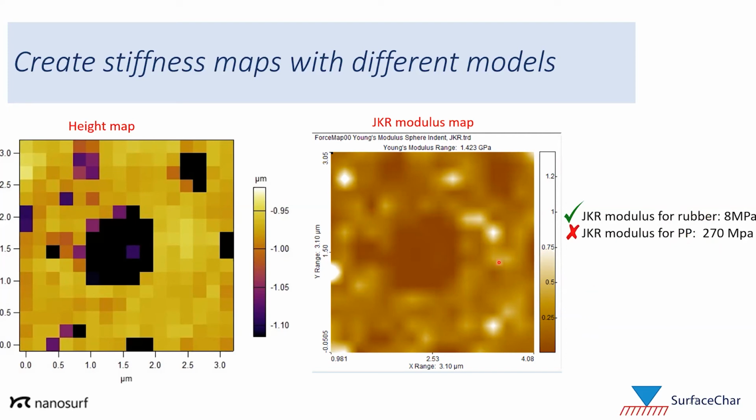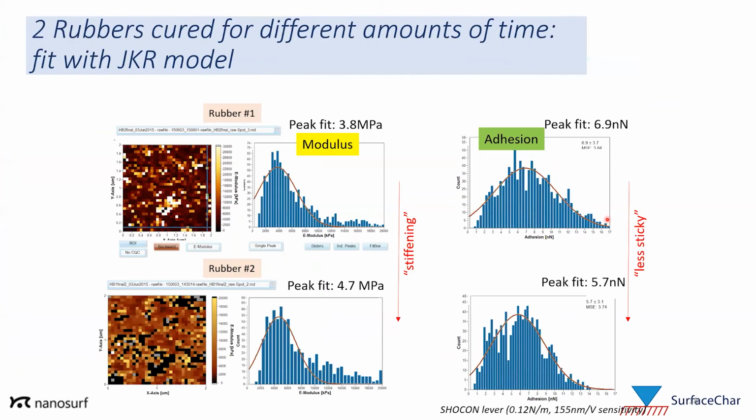This is an issue you run into very often, especially if you're looking at a sample that's very heterogeneous with a very wide range of mechanical properties in the AFM force curves. It can be hard to find one cantilever that suits all the different materials in your sample. Sometimes you have to optimize for one or the other. But again, this also shows the limitation of the models.